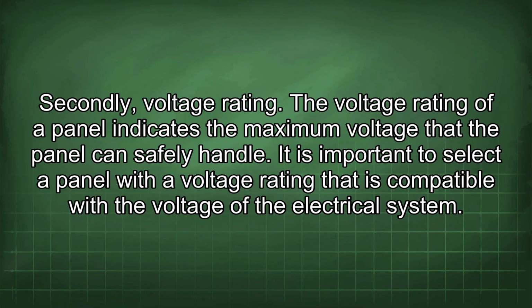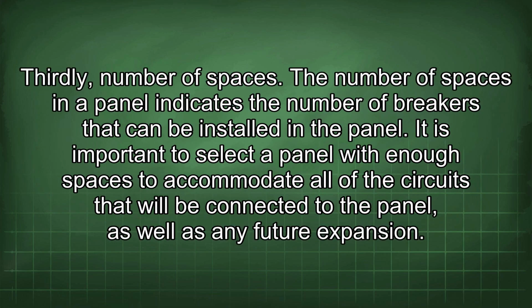Secondly, voltage rating. The voltage rating of a panel indicates the maximum voltage that the panel can safely handle. It is important to select a panel with a voltage rating that is compatible with the voltage of the electrical system. Thirdly, number of spaces. The number of spaces in a panel indicates the number of breakers that can be installed in the panel. It is important to select a panel with enough spaces to accommodate all of the circuits that will be connected to the panel, as well as any future expansion.